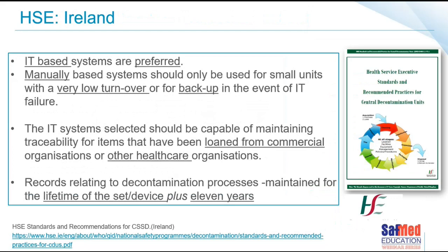The HSE guidelines state that IT-based systems are preferred, and manual systems should only be used for smaller units with very low turnaround or as backup in the event of IT failure. The IT system selected should be capable of maintaining traceability for items loaned from commercial organizations or other healthcare organizations — whatever system you're using, you need to be able to record loan sets. In Ireland, records relating to decontamination processes must be maintained for the lifetime of the device plus 11 years.